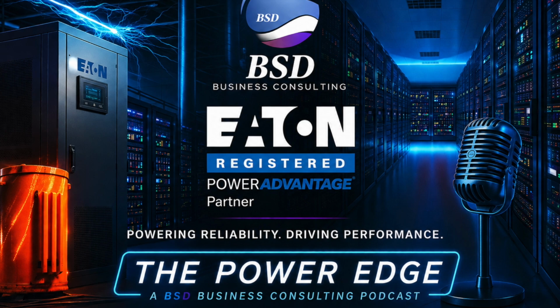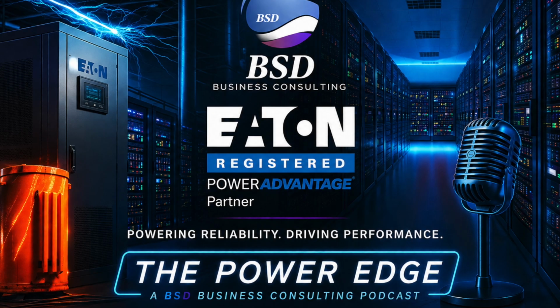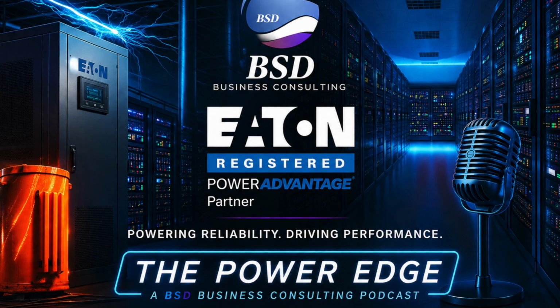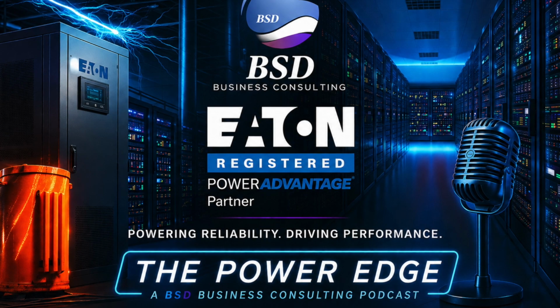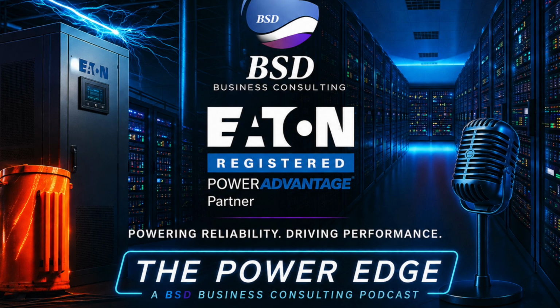Why is the shift to high-voltage direct current so important? Most data centers currently run on alternating current, right? Most do, yes. Power comes from the grid as alternating current, or AC. In a traditional data center, that AC power goes through an uninterruptible power supply, gets converted to direct current, or DC, for the batteries, gets converted back to AC, and then goes to the server, where the server's power supply converts it back to DC for the motherboard.